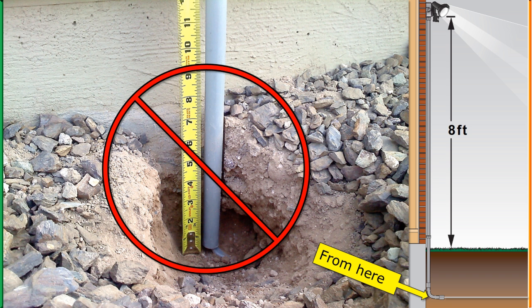In most cases, table 300.5 will tell you that that direct buried cable needs to be at least 18 to 24 inches deep. There are certain provisions that would allow it to go as shallow as 12 inches. But most of the time, 18 to 24 inches.